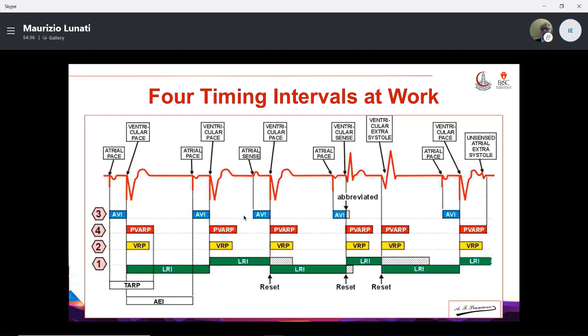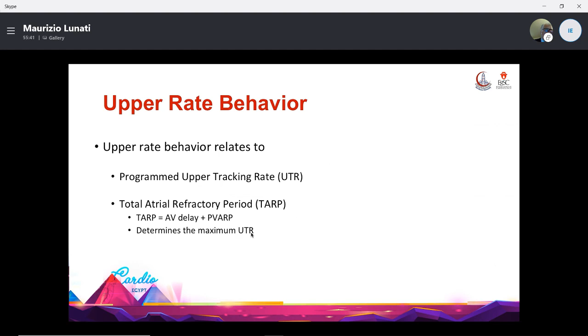What is the upper rate behavior? Upper rate behavior is related to a programmed upper tracking rate, which we can program after the implant or during the follow-up. We should know that the total atrial refractory period is the sum of AV delay and postventricular atrial refractory period. The sum of AV delay and of postventricular atrial refractory period defines the maximum tracking rate. What does this mean? In order to avoid too high frequencies during a natural tachyarrhythmia, the pacemaker has to limit the upper rate behavior, and the upper tracking rate is the rate over which the pacemaker cannot go.